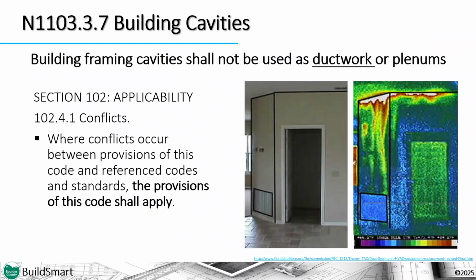The picture on this slide shows the potential impact of using building cavities as pressurized ductwork. In this ranch-style house, the return is pulling from the room as well as the attic on this hot summer day, thus making the HVAC system work harder and making it much more difficult to cool the house. Now, there is some conflict between the IRC and the Energy Code on this subject, but the applicability section of the code ensures that the requirement to not use building cavities as pressurized duct systems stands in Boulder County.